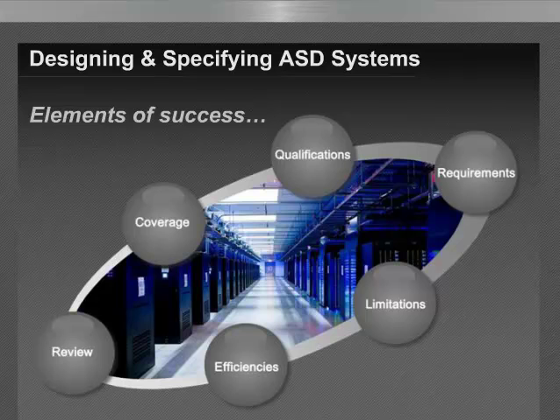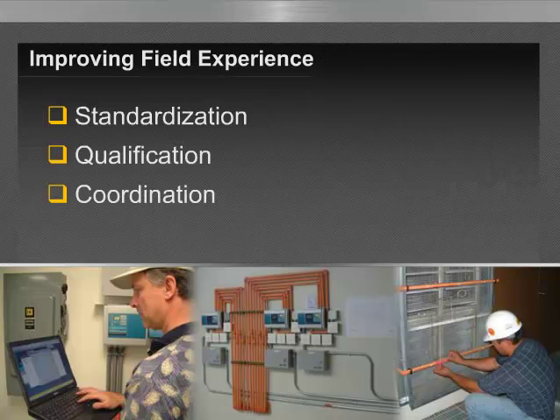So, improving the field experiences, we talk in terms of standardization, and that is adopting a master aspirating detection specification template when applying these types of detectors, or whichever type of detector is being applied, ensuring that there's standardization in regards to how it's specified. And again, qualification, we can't overemphasize the use of qualified system integrators, and coordination, and that is notification of projects early on while in the planning stages, keeping the manufacturer in the loop, and requiring the manufacturer's design review prior to submittals. All of this will help and aid in improving the experiences in the field and ensuring consistency site to site.